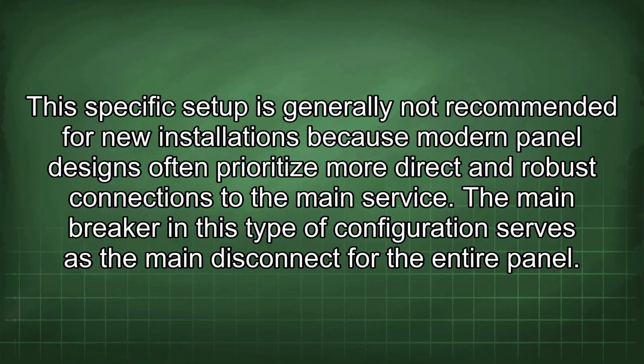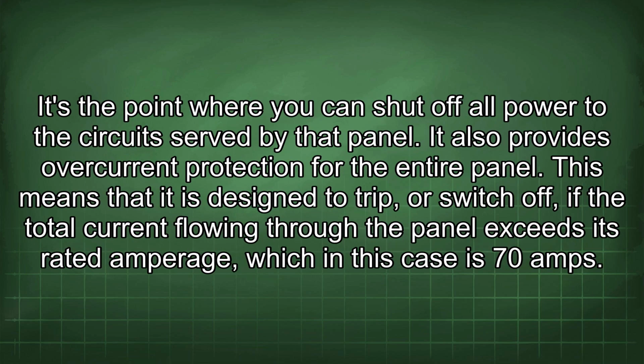The main breaker in this type of configuration serves as the main disconnect for the entire panel. It's the point where you can shut off all power to the circuit served by that panel. It also provides overcurrent protection for the entire panel. This means that it is designed to trip or switch off if the total current flowing through the panel exceeds its rated amperage, which in this case is 70 amps.